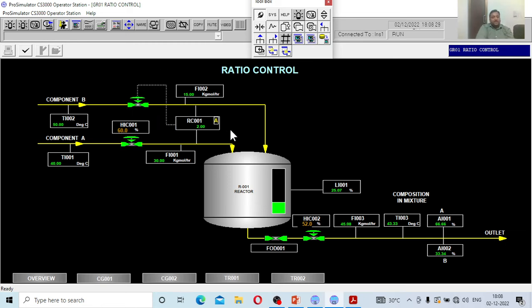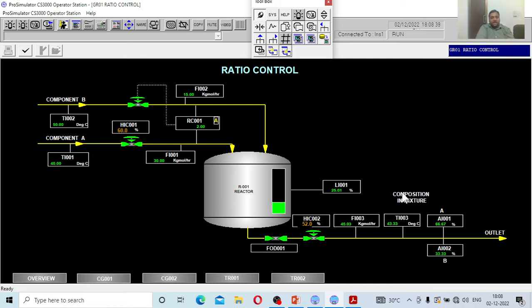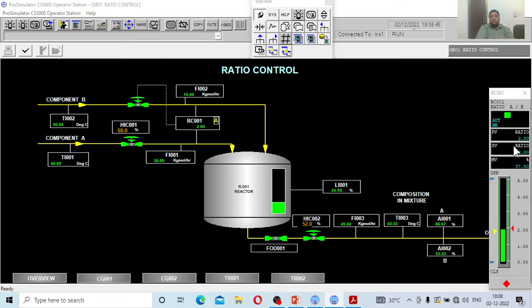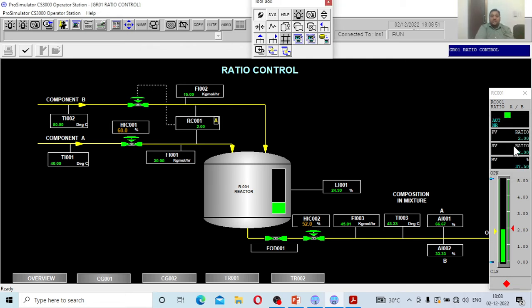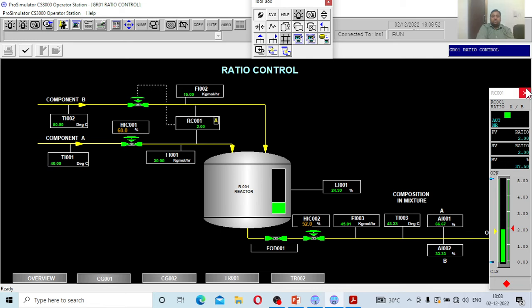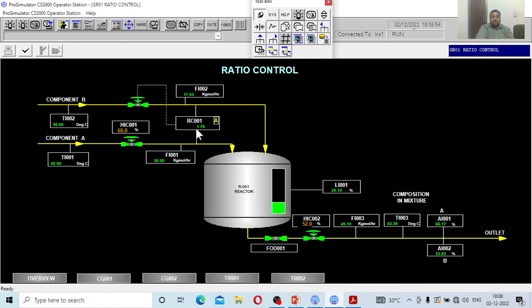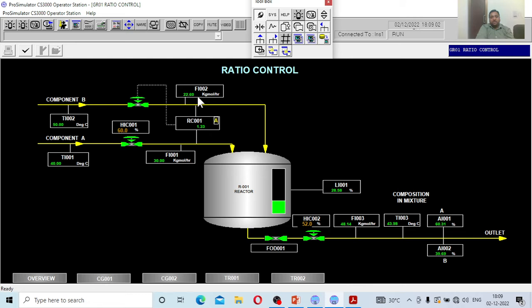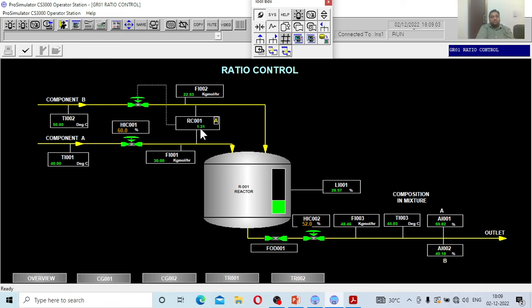You can do many things here. Right now I did the disturbance problem, now I do the servo problem. Everything got to steady state. Now I want to change the set point because I want to change my stoichiometric amount. The set point is 2, now make it 1. I want to send equal proportions of B and A. Now A is 30, B should also reach 30 because I have changed my set points.